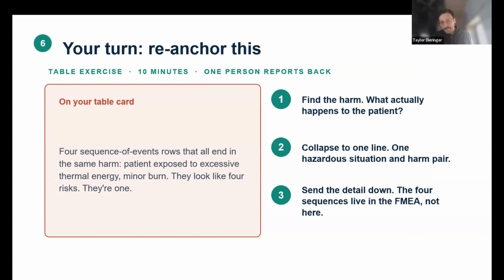But in regards to identifying hazards, I agree that in terms of 14971 and the technical report 24971, it doesn't necessarily give us a great means of identifying how to define hazards. The only thing that really exists, of course, is in Annex A as a checklist to identify what hazards may exist. But it doesn't really give us a framework for defining those hazards. And you'll see hazards defined very differently from one company to the next, usually based on how the very first one was defined. So again, I would refer back to that STPA process where they actually have a very specific and stochastic way of defining what an individual hazard is, and it does it very systematically.